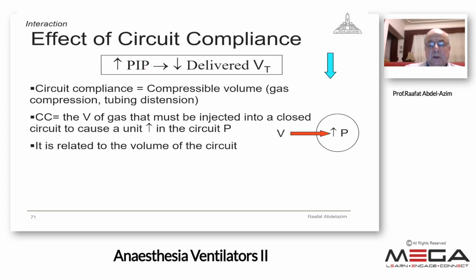The effect of circuit compliance depends on the compliance of the circuit, the material. The manufacturer will supply us with the compliance, that means how much the circuit will expand by volume in relation to the pressure. It is called circuit compliance. The first factor is the material, how compliant it is, and the other one is the peak inspiratory pressure. Whenever the pressure increases, the pressure will lead to more expansion of the circuit, and this leads to more loss, and the delivered tidal volume will be less.